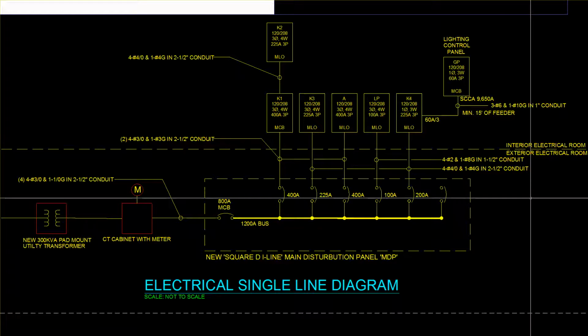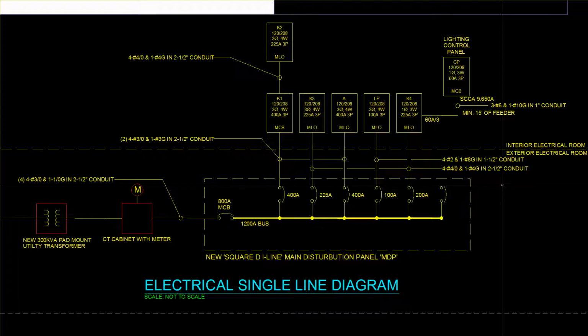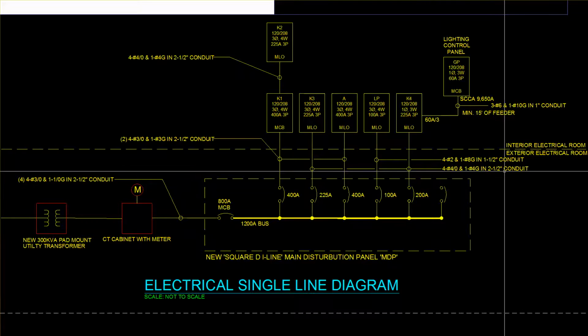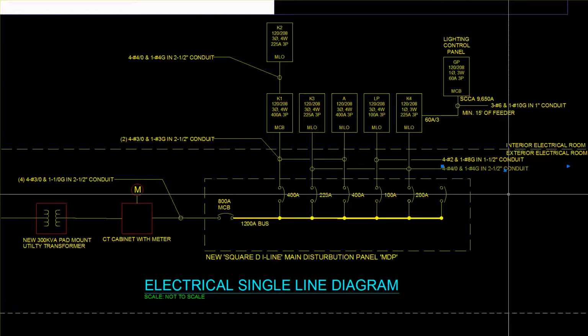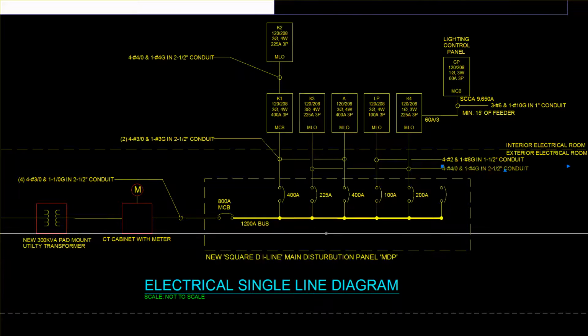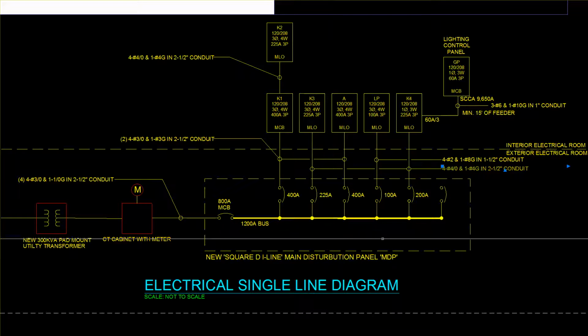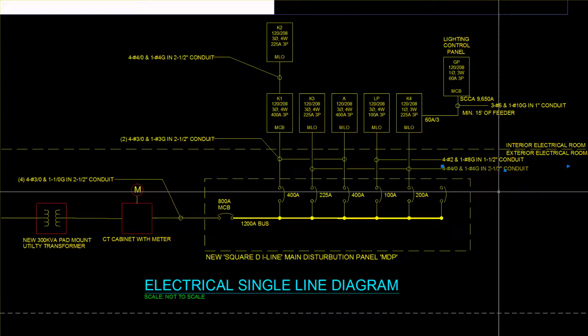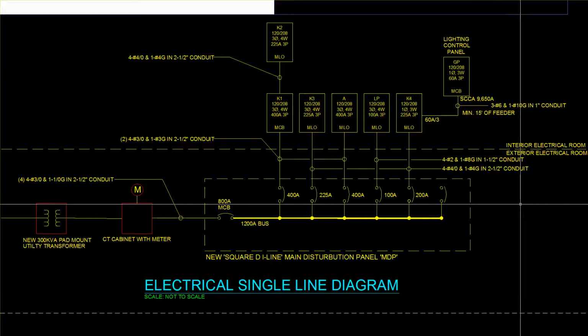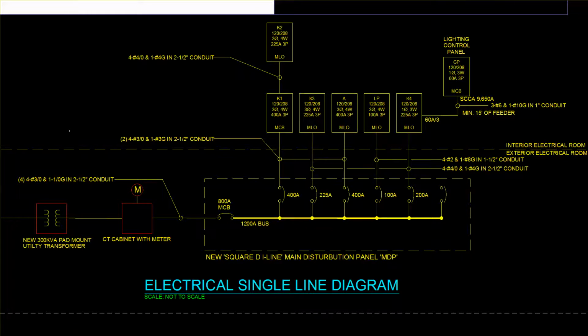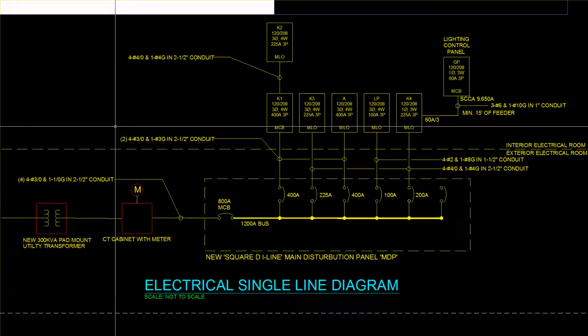And so when these are being reviewed and when these are being designed, we design these feeders to meet, at a minimum, the ampacity of the circuit breaker that's feeding them. Sometimes we'll enlarge these wires in order to accommodate, say, voltage drop or nonlinear loads, things along those lines. In this particular case, these are sized for the actual load that's going into these panels.